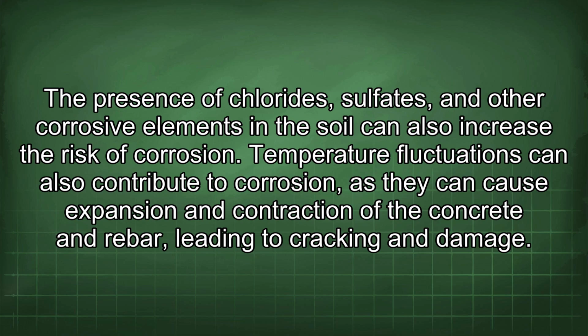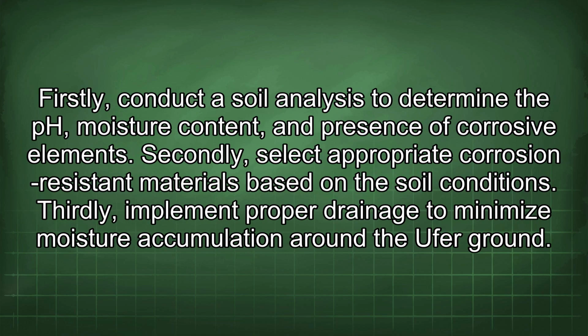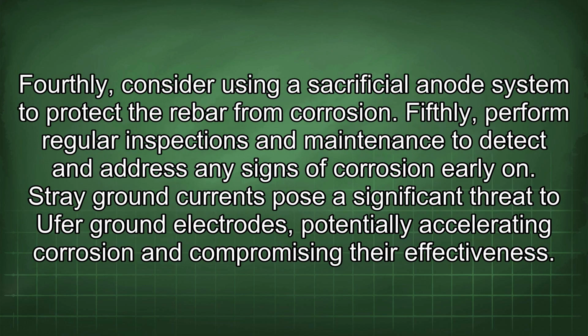Firstly, conduct a soil analysis to determine the pH, moisture content, and presence of corrosive elements. Secondly, select appropriate corrosion-resistant materials based on the soil conditions. Thirdly, implement proper drainage to minimize moisture accumulation around the Ufer ground. Fourthly, consider using a sacrificial anode system to protect the rebar from corrosion. Fifthly, perform regular inspections and maintenance to detect and address any signs of corrosion early on.